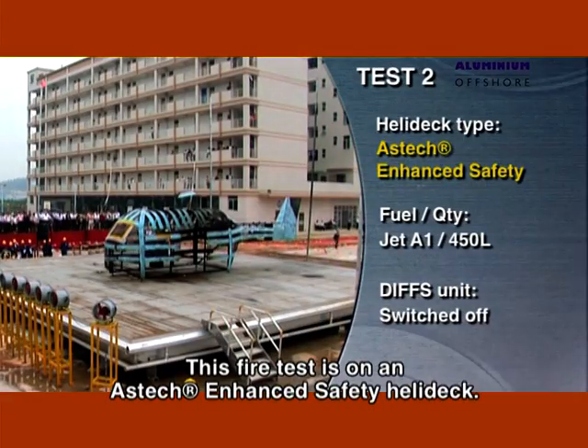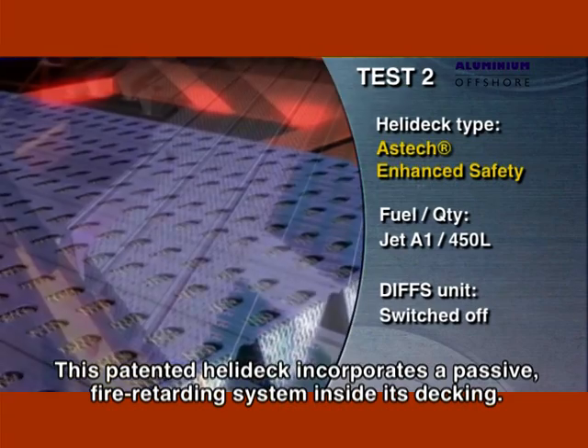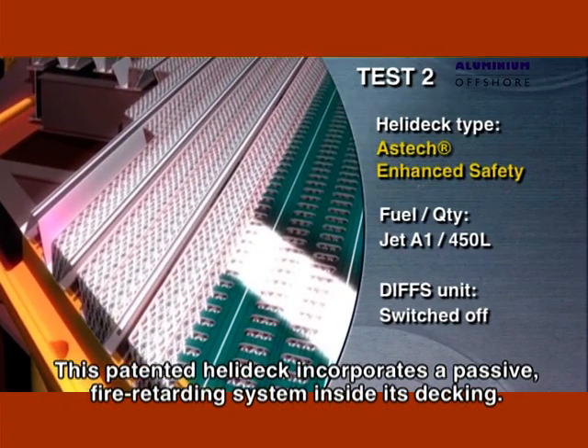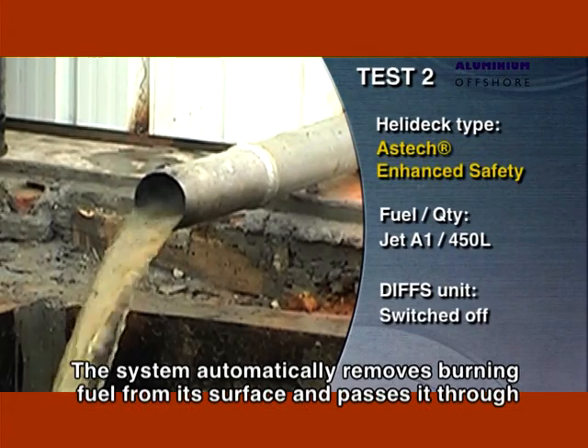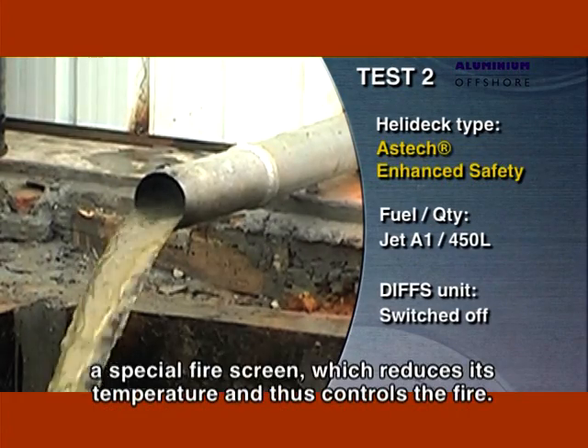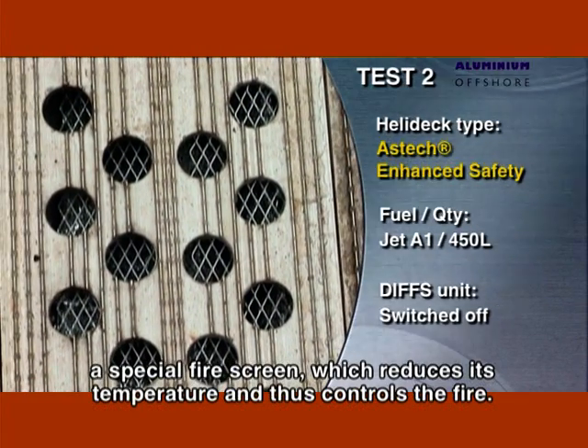This fire test is on an Astech® Enhanced Safety helideck. This patented helideck incorporates a passive, fire-retarding system inside its decking. The system automatically removes burning fuel from its surface and passes it through a special fire screen, which reduces its temperature and thus controls the fire.